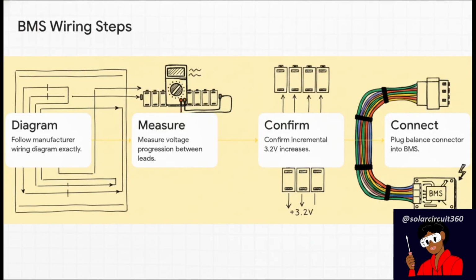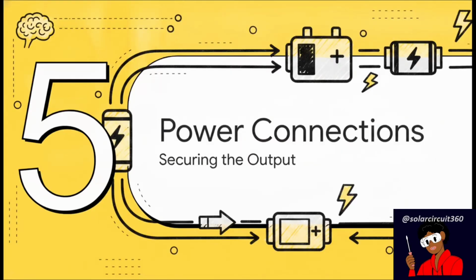To wire it up safely, you must follow the manufacturer's wiring diagram exactly. Seriously, plugging in that main wiring harness is the point of no return. You've got to treat this like a strict pre-flight checklist. Grab your multimeter and measure the voltage progression between every single lead point. What you're looking for is to confirm an incremental 3.2 volt increase at each step. If, say, step 4 shows 6.4 volts instead of the 12.8 volts you're expecting, stop immediately. Never guess on this. You must sequentially verify every single voltage sequence before you even think about plugging that balance connector into the BMS. All right, moving right along to Section 5, fuses and power connections, securing the output.